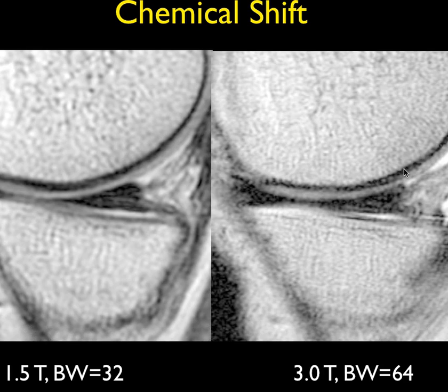Okay, now, if you remember what I said a little bit ago, if we have bandwidth, let's say it's 15 kilohertz, you want to arrange the bandwidth so that you get the signal from the left side of the body and the signal from the right side of the body. I think it's going to be increased noise then. Okay. You don't want to get any signal outside that range because it's only going to be noise. The bottom line is, as you increase the bandwidth, you're going to bring more noise into it because there's a background of noise spectrum that's across the entire spectrum.